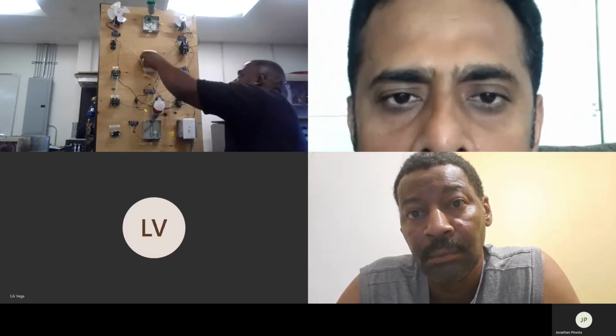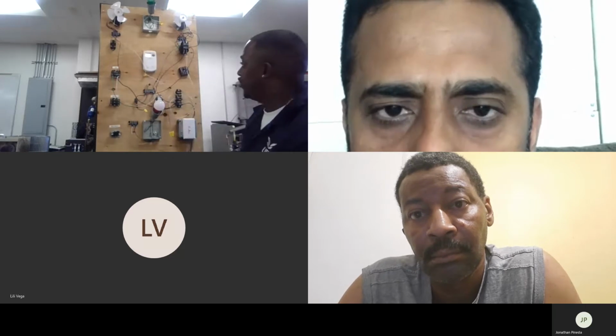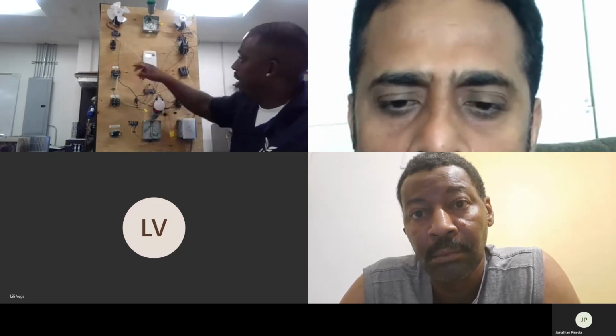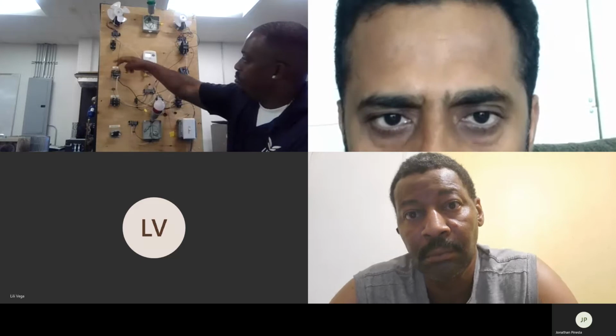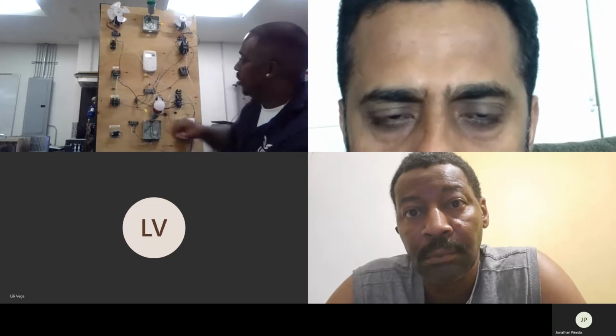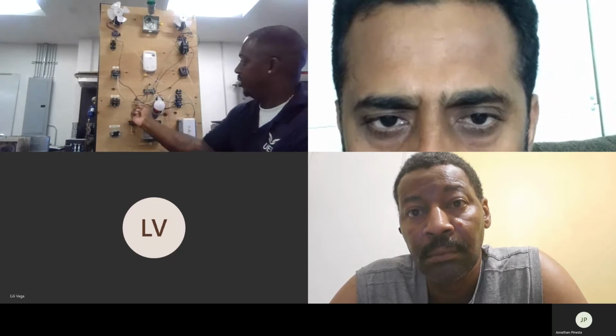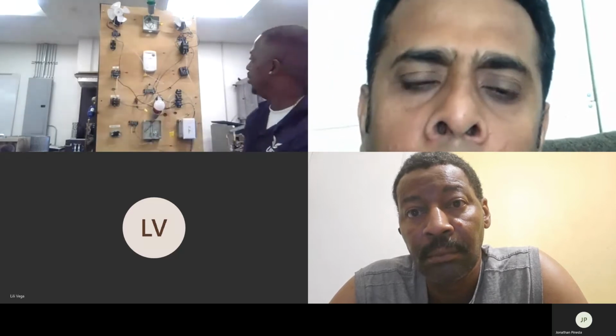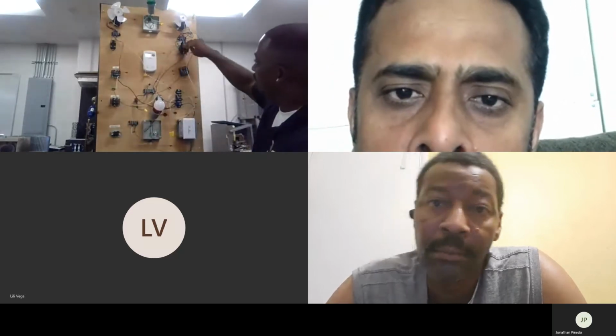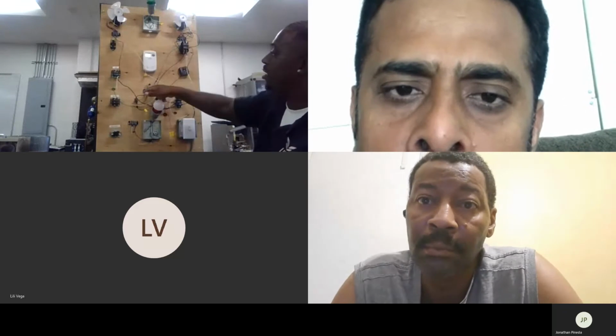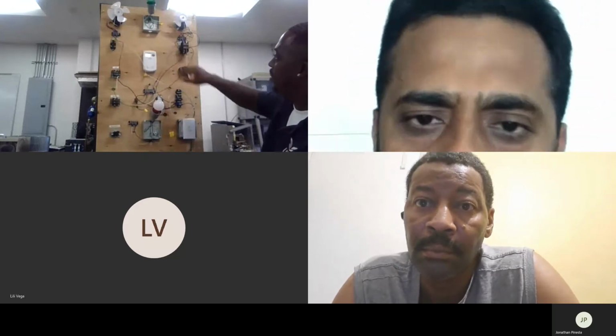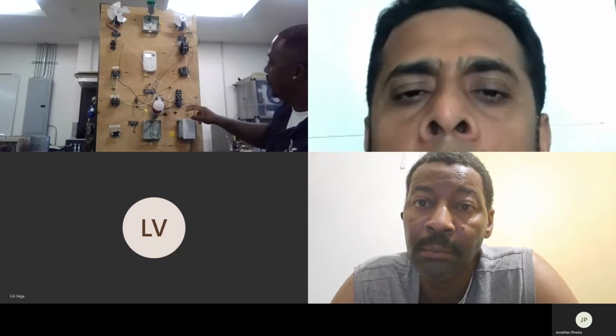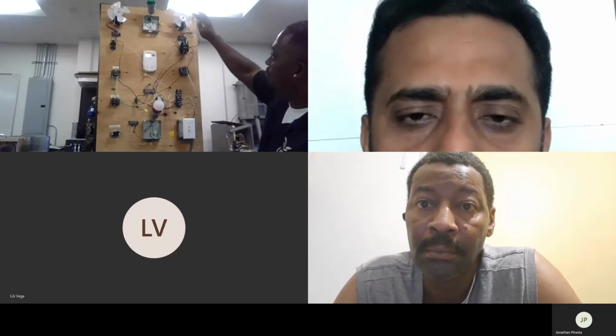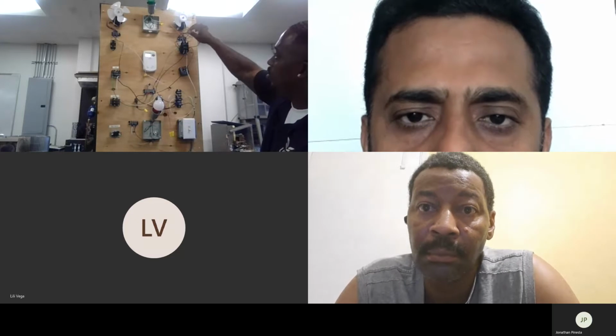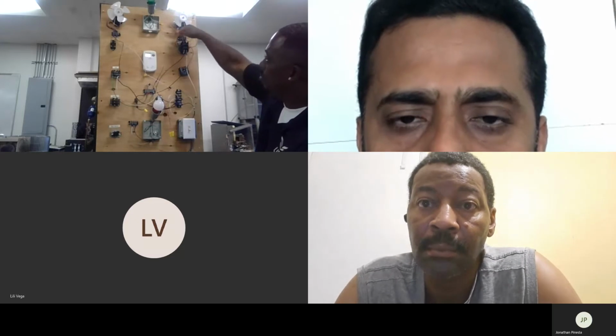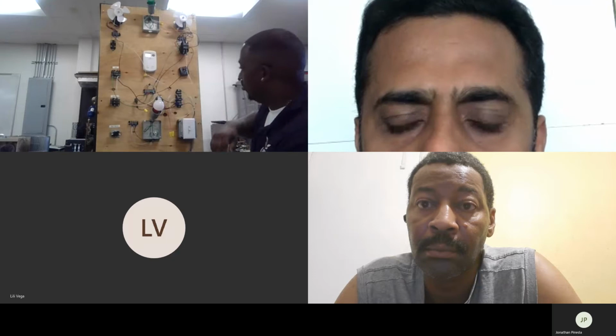So that's just a quick recap. We have our 120 which is going to pass to our high speed. We have our coil voltage that's going to energize when G gets energized. We have our G in common. Same thing over here, our coil is going to energize when Y is energized for cooling, so we have our Y and our common. We've got our hot and neutral coming in from L1 and L2, and then we have 4 wires going to T1 and T2, two from our light, two from our fan. So everything's ready to go.